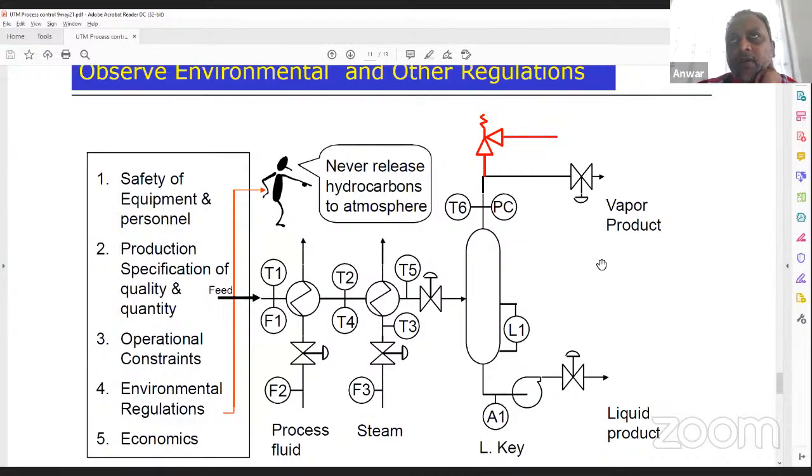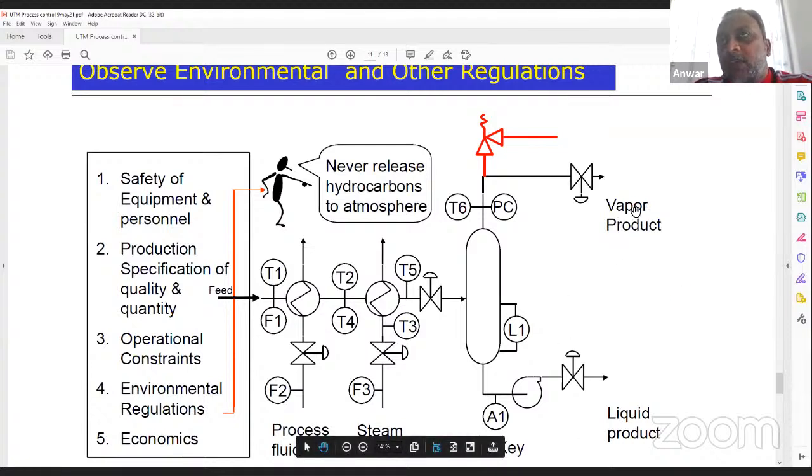Example, to have pH monitoring, because for standard B, we should be discharging the liquid effluent after adjusting the pH in between 5.5 to 9 maximum. So this is the requirement to be observed in terms of regulation. Okay.